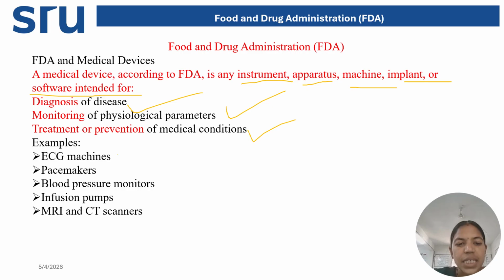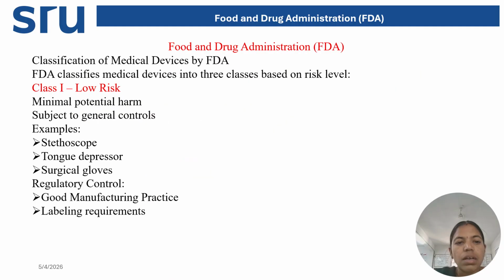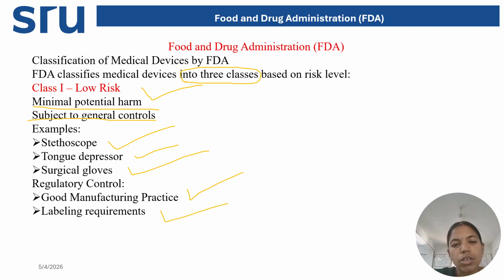The examples are ECG machines, pacemakers, BP monitoring machines, infusion pumps, MRI, and CT scanners. Classification of medical devices by FDA. FDA classified the medical devices into three categories based on the risk level. First category, as discussed, low risk. It causes minimal potential harm to the patient and it is subject to general controls. Examples are stethoscope. With a stethoscope, we can check our heart rate any number of times. It will not cause any harm to the patient. Tongue depressor, surgical gloves, and what are the regulatory aspects we have to check: they are manufactured under good practices and labeling is also required.